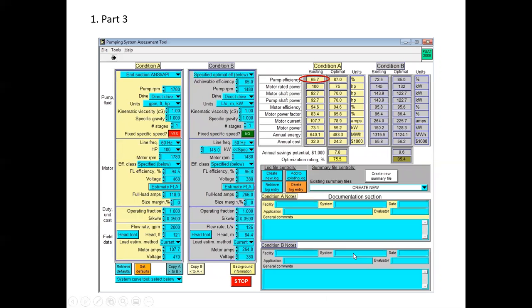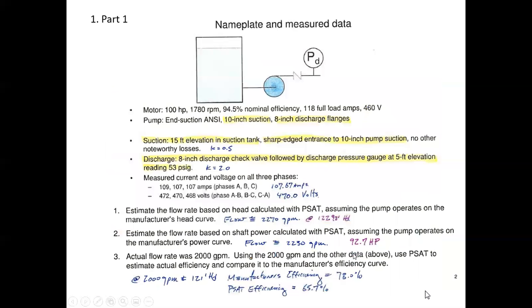So let's see, I guess we need to go back then. So however you read that, 2210 to 2230, something like that, at this horsepower. But that's how you do number 2. And then number 3, we want to put in the actual flow rate of 2000 GPM and the other data that we need, the pipe sizes and all that. Use PSAT to estimate the actual efficiency and compare it to the manufacturer's efficiency.